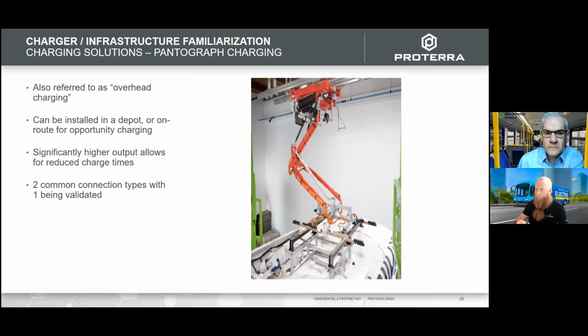These overhead fast chargers, DC fast chargers, allow for a higher output from the charger itself and faster charging windows on the bus. Keep in mind that at a certain point it does derate, so you're not going to continuously output, let's say, 500 kW to the bus at all times. There's a small window where that fits; otherwise it derates into a certain window where we're trying to prevent overheating of the batteries and any damage or degradation of the battery cells.